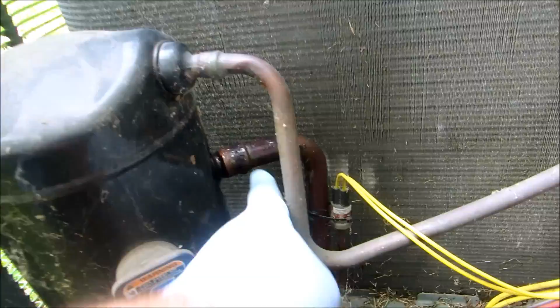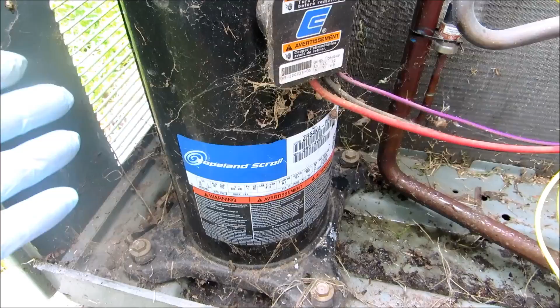Alright guys, you can see how the suction line's sweating, but this compressor's not sweating—see how it's dry? That's what you want to see. You never want to see a compressor sweat. If you see a compressor sweat, that means it's flooding back and it's not charged properly. So you see this compressor's dry, no water on it. It's refrigerant cooled, so it'll get cooled off by the refrigerant line, but the compressor itself isn't sweating. That's a little tech tip.